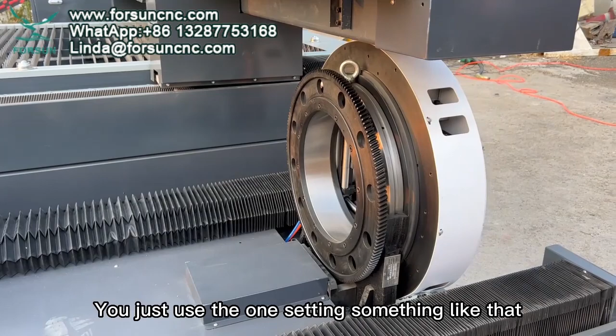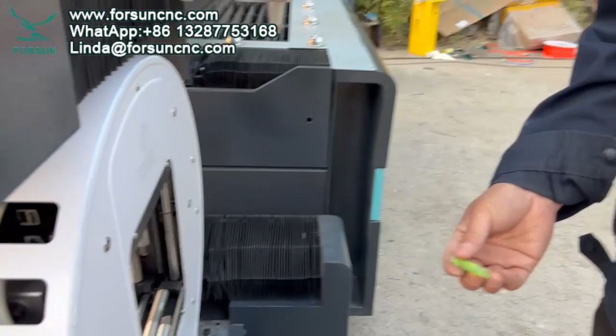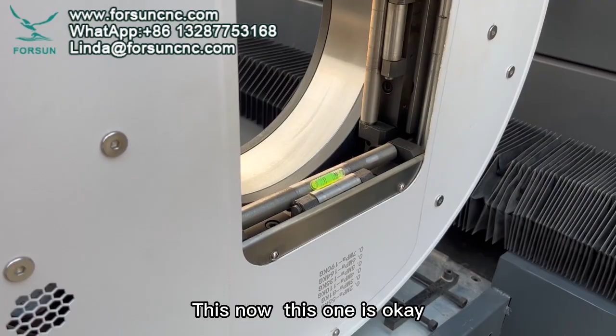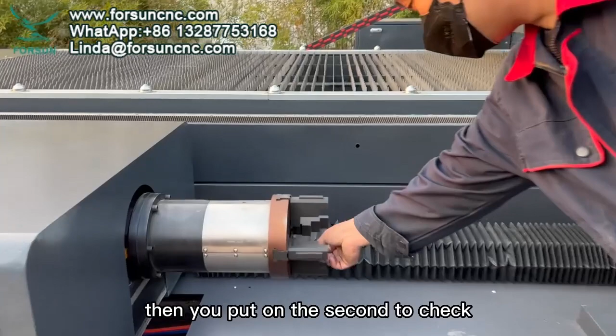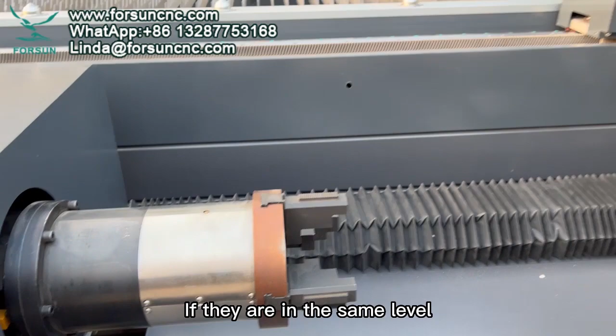How to set it at the same level? You just use the one setting, something like that. This is the levelization. Put it there. You find out, okay, this one is okay, this is on the same level. Then you put it on the second to check. If they are at the same level, then no problem, you can use it. But if they are different, then you must power off the machine and use your hand menu to adjust it. Adjust the back side or the front side. Any side is okay. Make them at the same level.